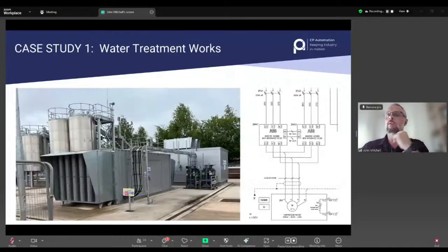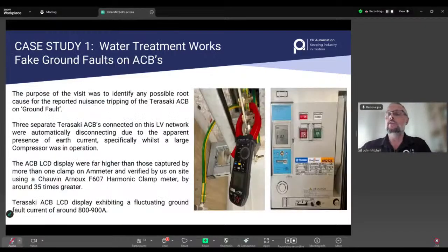So why don't we show you a few cases that we've solved problems for. This is a compressor for a water treatment plant, 2 ABB drives back to back, controlling a 630 kilowatt compressor. The drives were low harmonic, and what they were doing was creating a common mode noise that was affecting the Terasaki ACB. The ACB thought it had a ground fault of 816 amps.